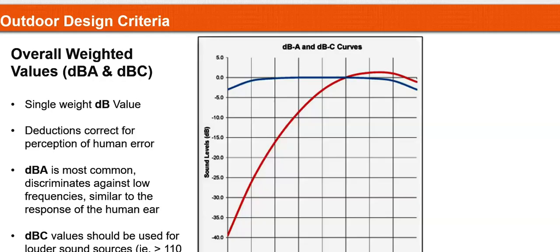Whenever you're talking about meeting a particular noise ordinance at a residential building or a school, have in mind that if it's outdoors, you're going to have to use dBA or dBC. dBC is typically used for peak or impact sounds, or sounds so loud that they could create instant hearing loss. So you'll see ratings for anything above 110, 120 decibels in airports, airplanes. All those will use C weighting, which means performance is not adjusted to human ear sensitivity, because even though some frequencies may not appear as loud to us, they could be detrimental to human hearing.